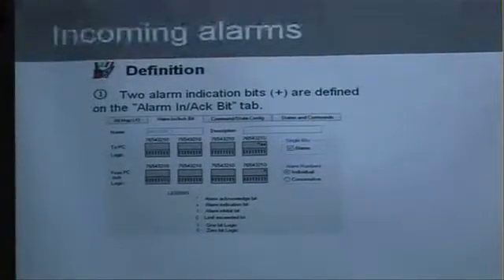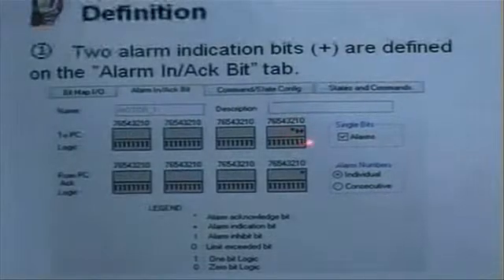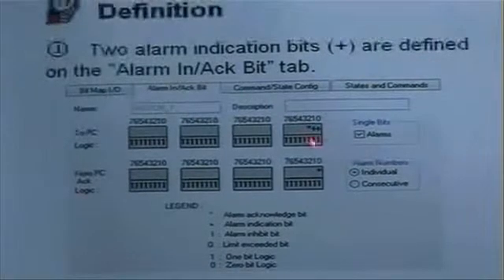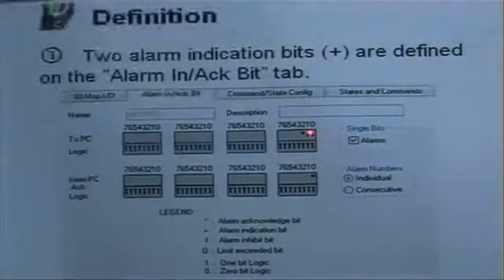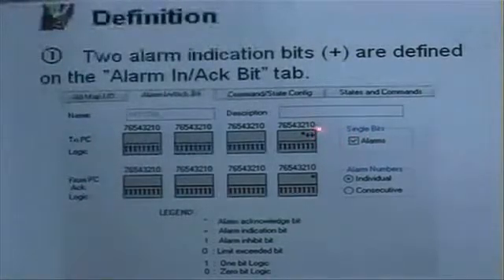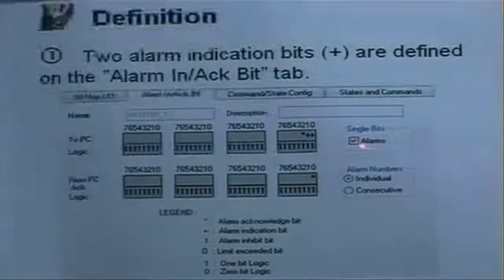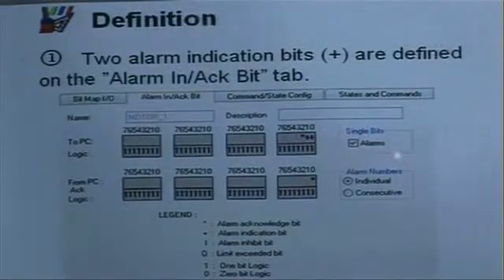First, I go into the To PC section and I define two plus signs as you can see here on bits 0 and 1. Those are the two digital alarms that are located in the PLC and I want them to come into the IGSS alarm list. Also, I select the single bit alarms checkbox to make it possible for these two alarms to occur simultaneously in the IGSS alarm list.